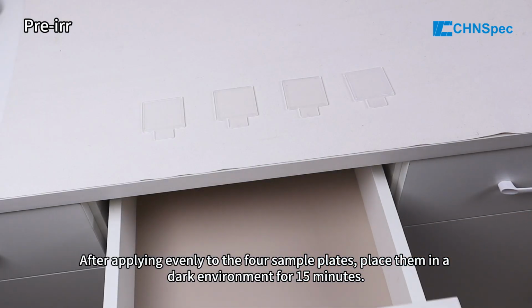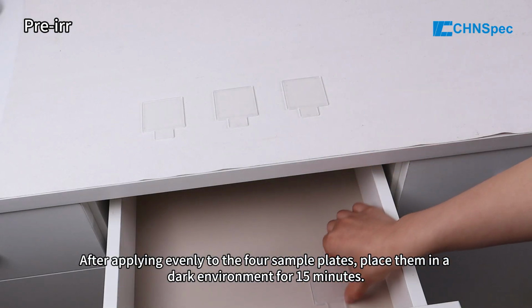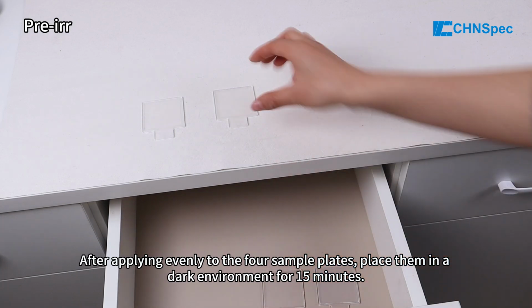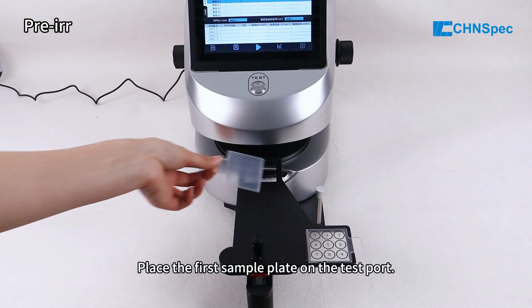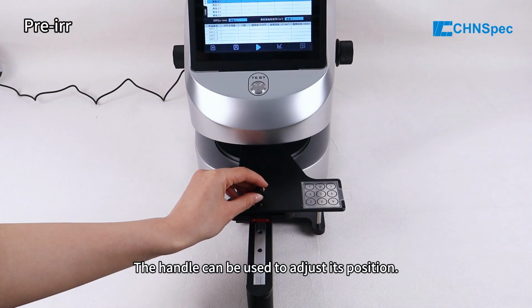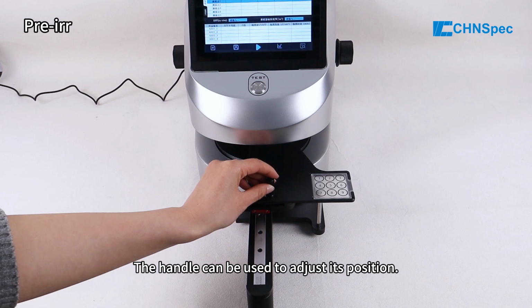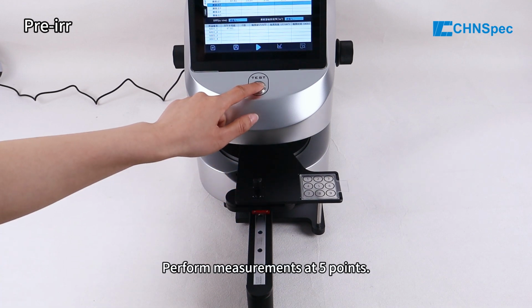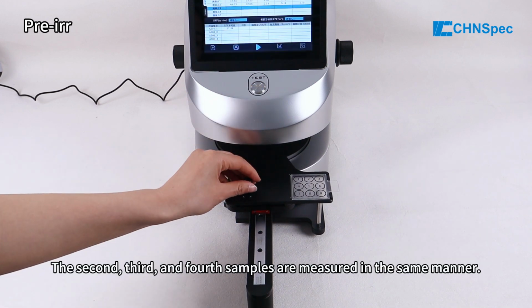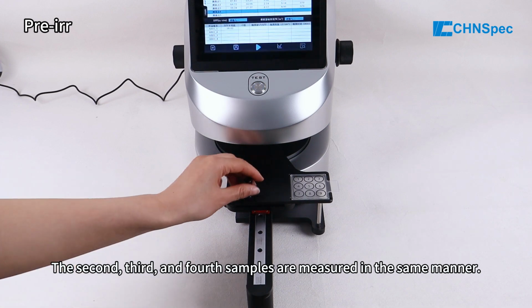After applying evenly to the 4 sample plates, place them in a dark environment for 15 minutes. Place the first sample plate on the test port. The handle can be used to adjust its position. Perform measurements at 5 points. The second, third, and fourth samples are measured in the same manner.